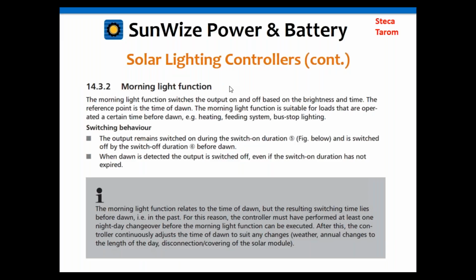So basically what this will do is it will switch on the load a certain amount of time before dawn. You'll note this is for some fairly specific applications, but if you wanted to run a heater or a feeding system or bus stop lighting for a certain amount on just the morning, it has that early dawn programming capability. Now, the nice thing about this is that there's actually memory behind these units in terms of remembering the shift from seasons and other things. So once you run this a single time, it will use that morning information to then be able to execute the programming. It needs to go through, as you see in the note here, at least one cycle. But after it goes through that single cycle, then it will continually adjust the time of dawn to account for, like I said, annual changes to the length of day, weather, and other details like that.